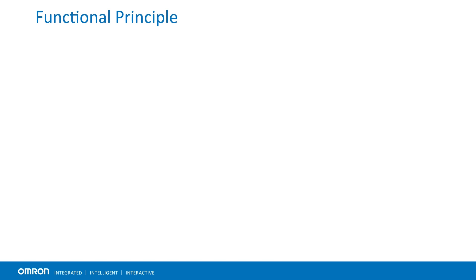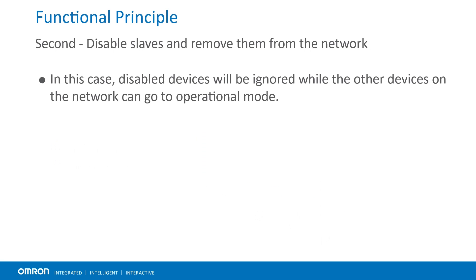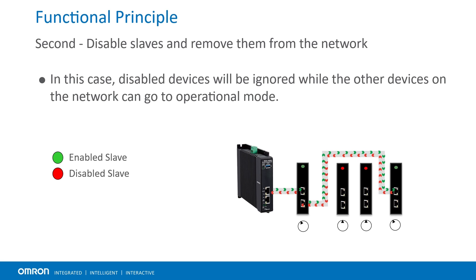The disable function can be implemented in two ways. First, disable slaves while the devices are physically present on the network — in this case, disabled devices will be set to pre-operational mode while other devices on the network can be set to operational mode. Second, disable slaves while the devices are removed from the network — in this case, disabled devices will be ignored while the other devices on the network can go to operational mode.